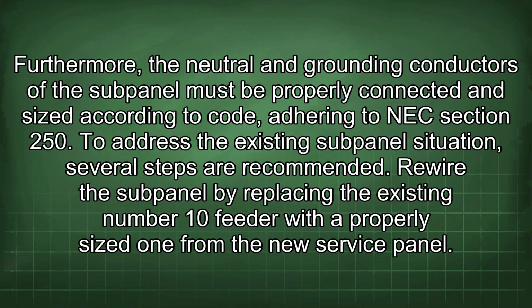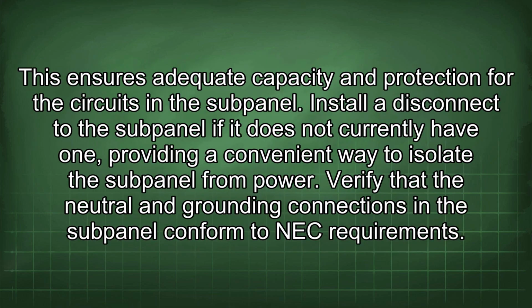384.16b. Furthermore, the neutral and grounding conductors of the subpanel must be properly connected and sized according to code, adhering to NEC Section 250. To address the existing subpanel situation, several steps are recommended. Rewire the subpanel by replacing the existing number 10 feeder with a properly sized one from the new service panel. This ensures adequate capacity and protection for the circuits in the subpanel.